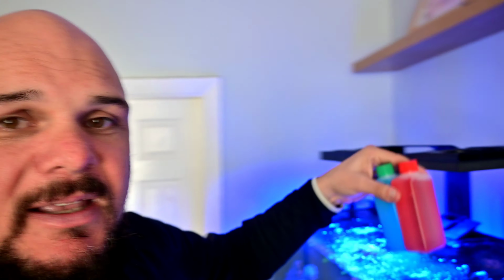So what I did was I bought the liquid forms, the green bottles. I'll just see if I can get them now. I bought these bottles here. Basically I stick them in my sump or my tank maybe half an hour before I'm ready to test, and there they are. This is a 0.4 and a 0.7, and I just stick them in the tank like this, leave them in for about 20 to 25 minutes, and when it's heated up to the temperature, then I calibrate it that way. And I seem to get a more accurate reading than I did with the powder.